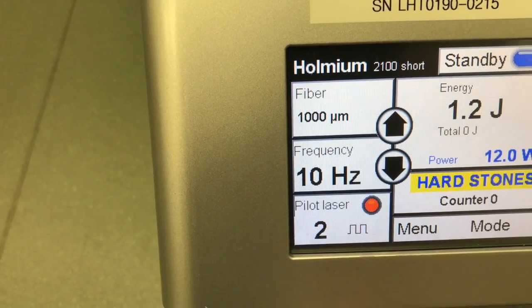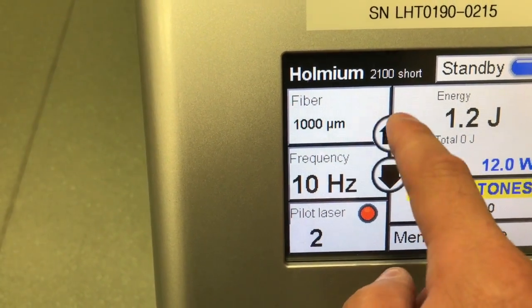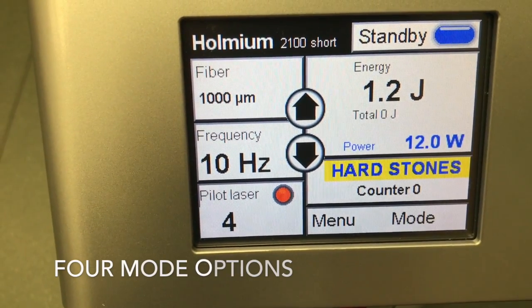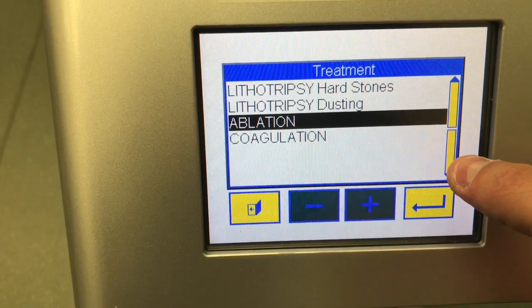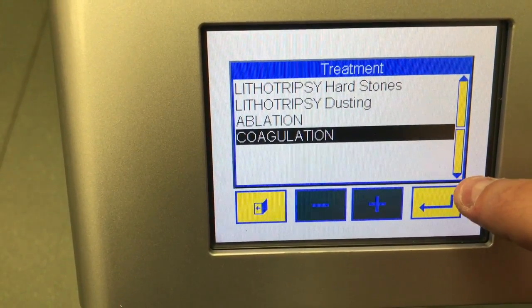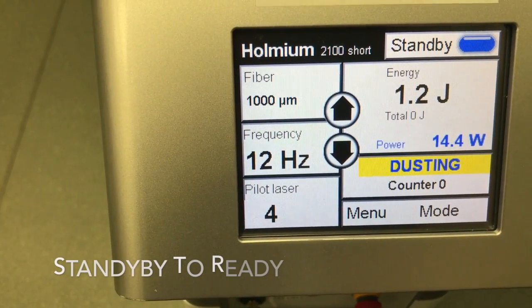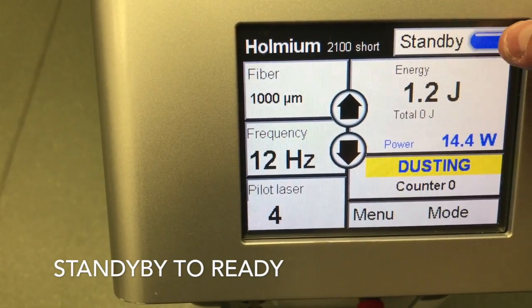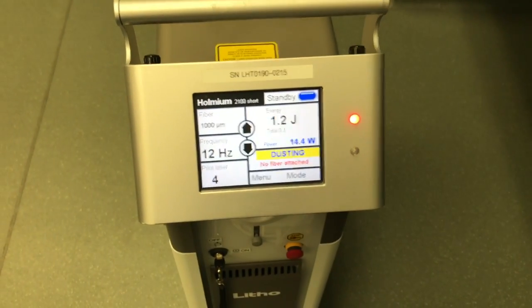The pilot laser is the aiming beam — it shows as a solid beam, and that little line signifies it's pulsating. For mode, this is currently in hard stones mode; you can also go into dusting, ablation, and coagulation. From there you're ready to go from standby to ready, and that is it.